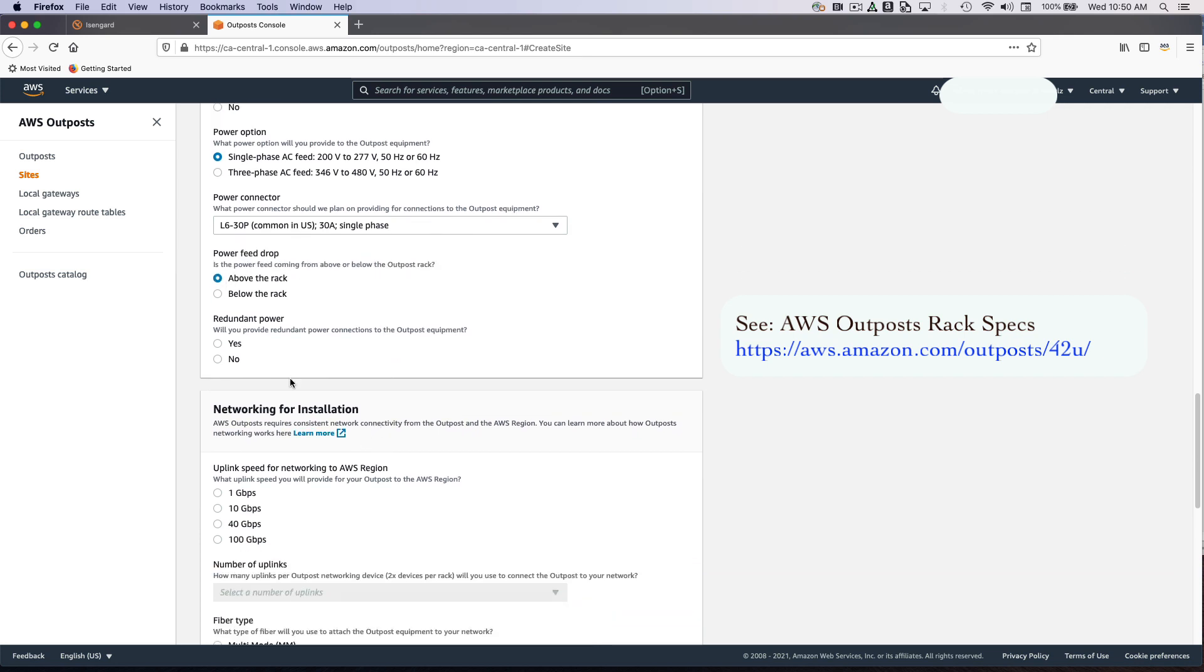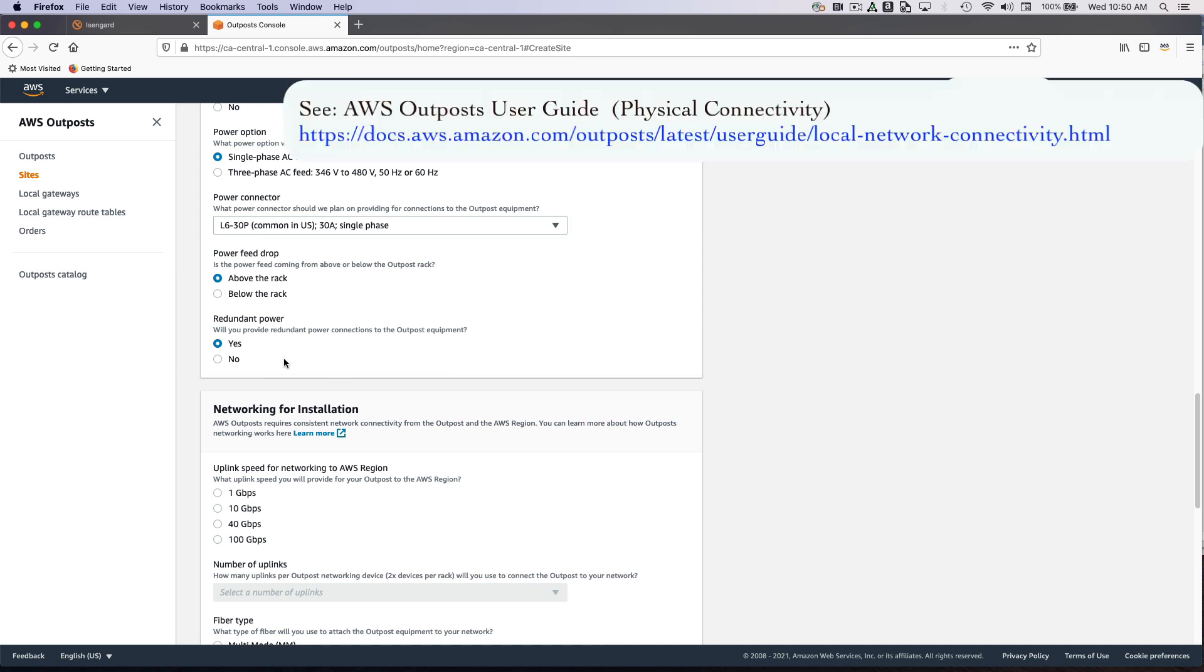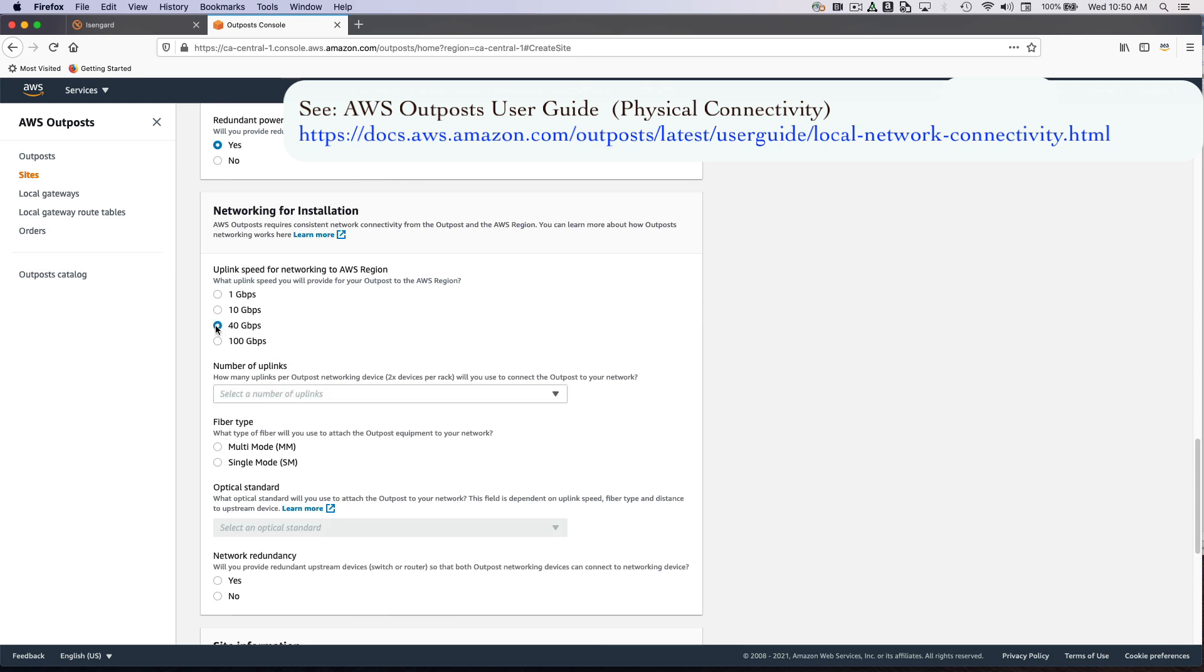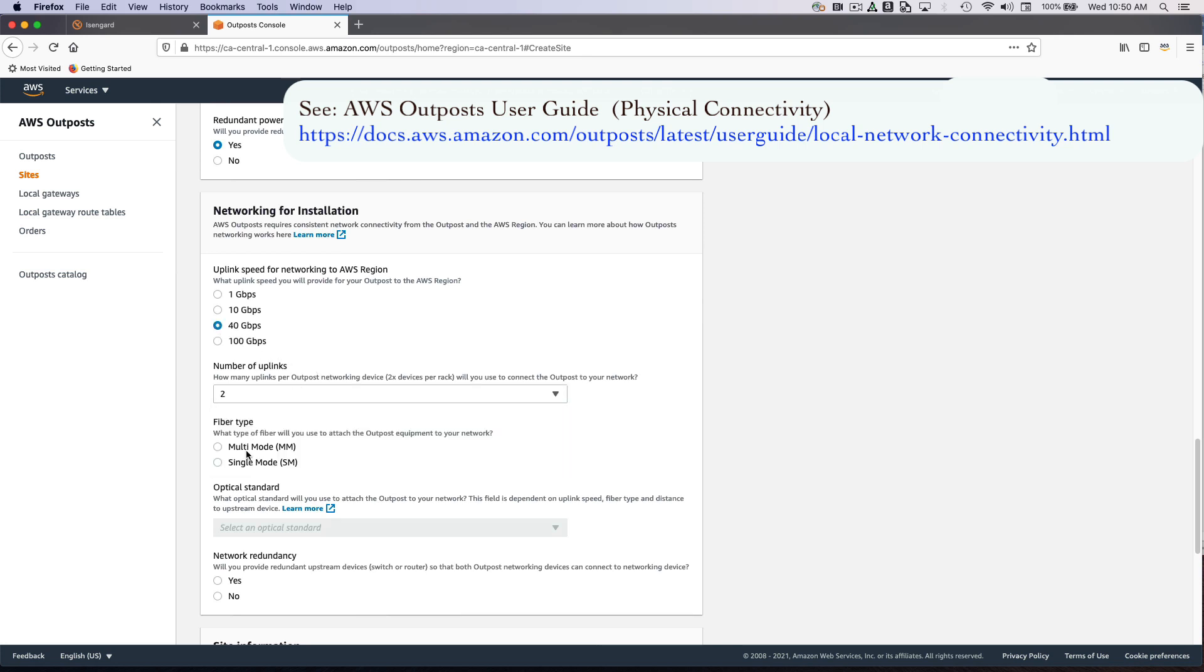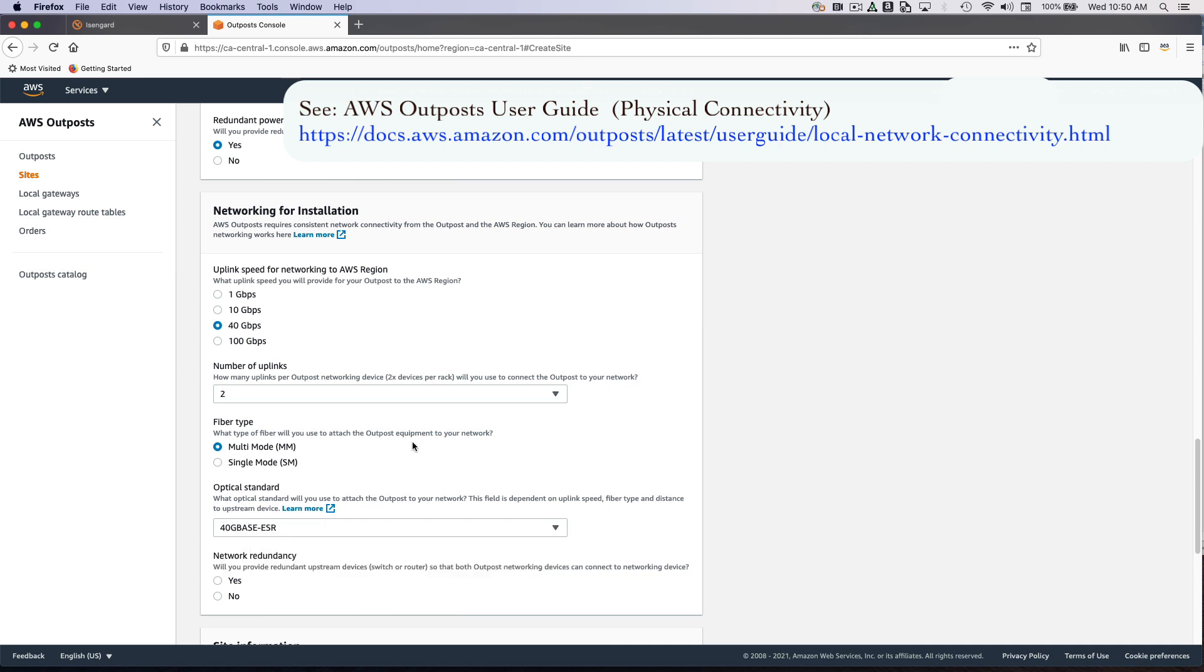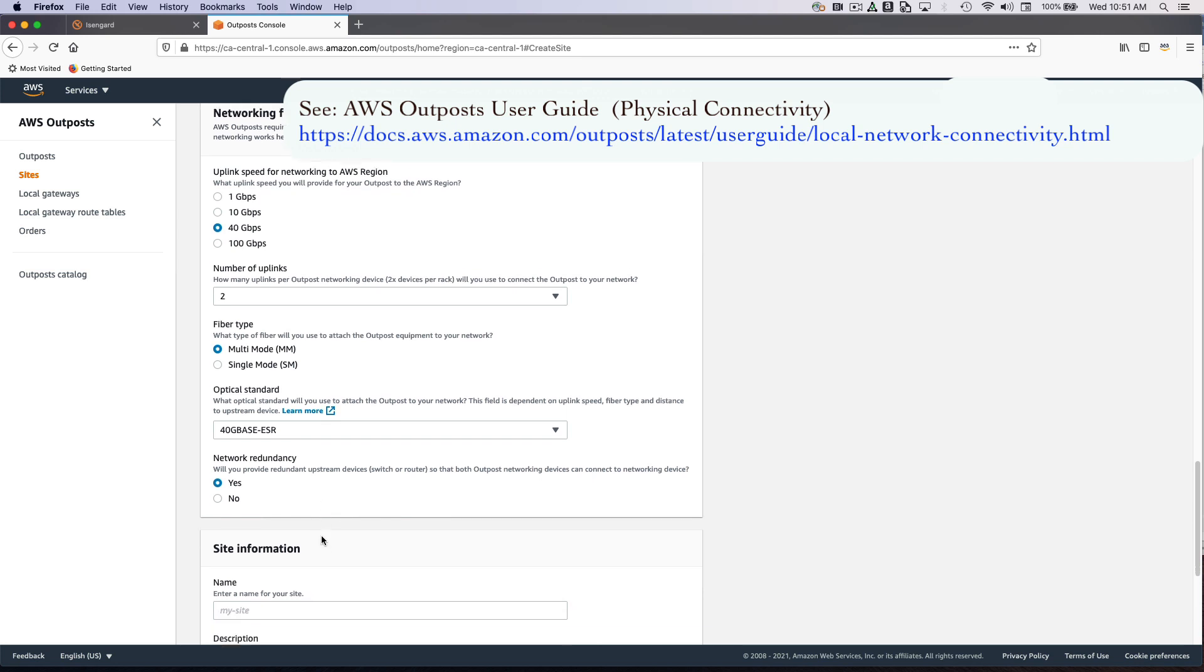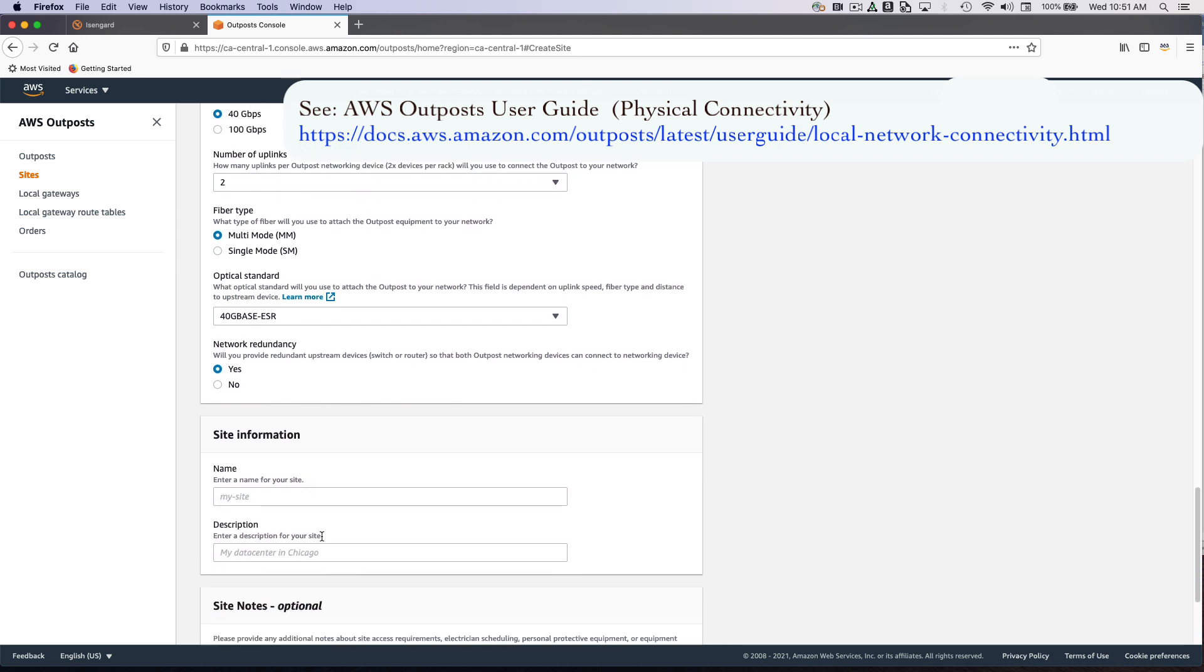We want to understand whether the power feeds are coming from under the cabinets or above the cabinets, and whether you'd like to provide redundant power. All Outpost configurations come with support for redundancy for networking and power, but it is really up to you to let us know whether you will be providing that or not. Moving on to the networking section, I'm going to select some values. When discussing numbers of uplinks, this is a reference to the number of uplinks for each Outpost networking device up to the demarcation point that connects to your switches on-premises. A minimum of two is required because that contributes to a total of four, and that's the minimum redundancy we recommend.